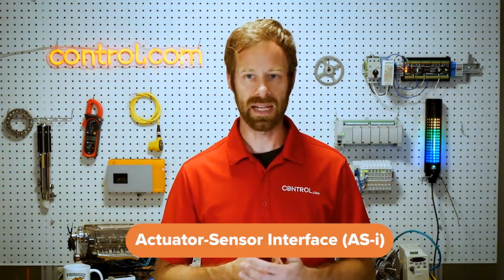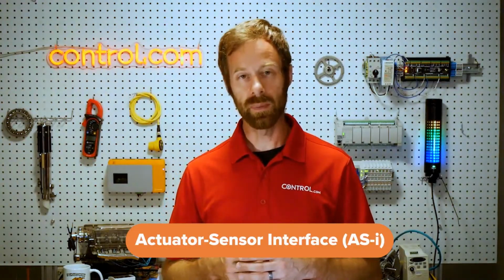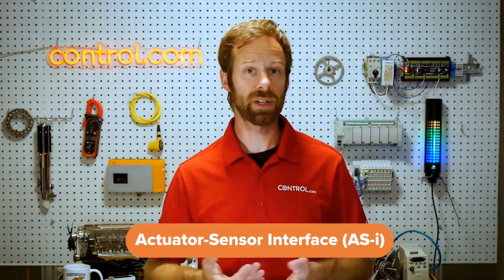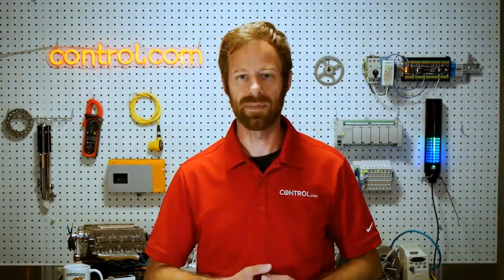Another one that is popular in some areas is called the Actuator Sensor Interface, or ASI. This one is a bit simpler in architecture than Modbus because it uses only a keyed two-wire communication between a gateway, which is a device that connects one protocol level of sensor to a higher level, which means the PLC's level. So it might be converting Ethernet or Profinet to this ASI, Actuator Sensor Interface, level.